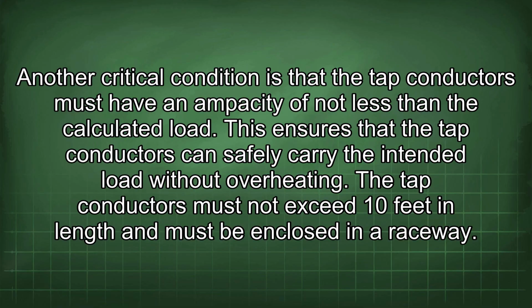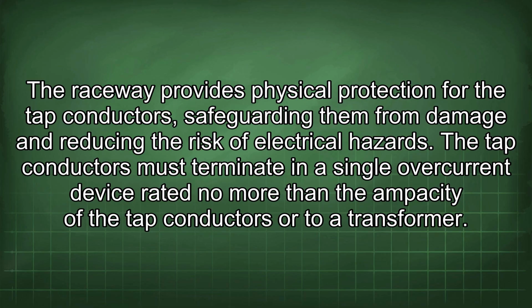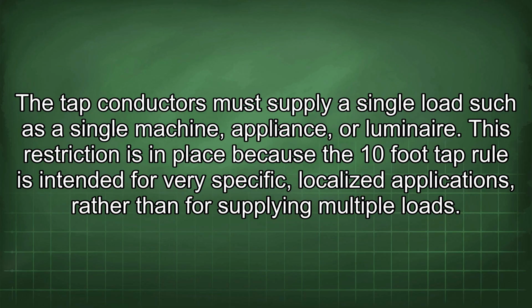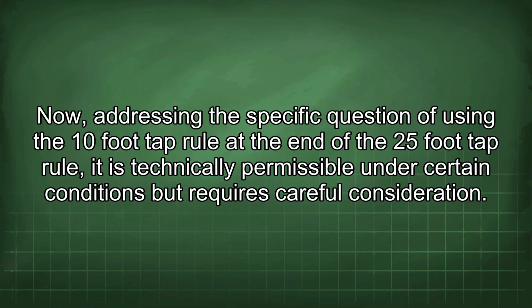The tap conductors must not exceed 10 feet in length and must be enclosed in a raceway. The raceway provides physical protection for the tap conductors, safeguarding them from damage and reducing the risk of electrical hazards. Tap conductors must terminate in a single overcurrent device rated no more than the ampacity of the tap conductors or to a transformer. The tap conductors must supply a single load such as a single machine, appliance, or luminaire. This restriction is in place because the 10-foot tap rule is intended for very specific, localized applications rather than for supplying multiple loads.